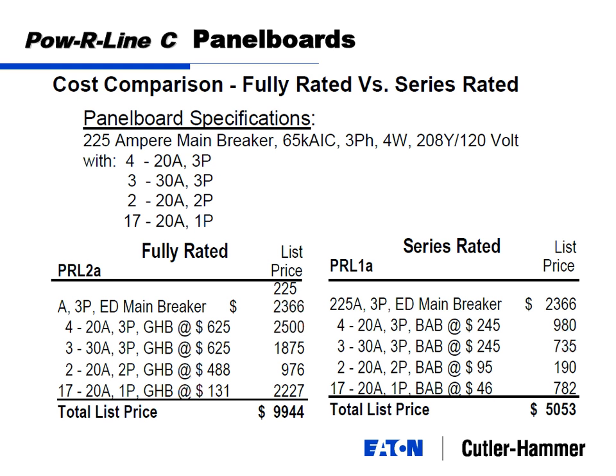As an example, I got 225 amp main breaker, which is this size here, 65K. This is pretty much the example we touched on. 120, 208 volt with an assortment of feeder breakers. We've got fully rated and series rated, priced out in different panel board styles. Both panels will have the same 65 kA breaker, same price. And using the full 65K feeder breakers, I add up to just shy of $10,000 list price. And if I use these BAB 10,000 amp rated breakers, notice they're a fraction of the cost. And adding up the price, you're around $5,000, so you're roughly half the price for series rated versus fully rated.